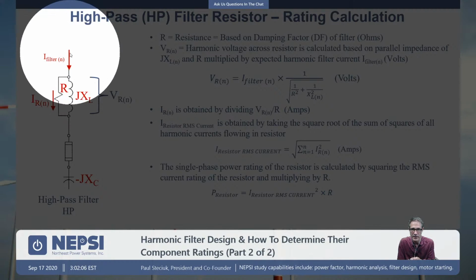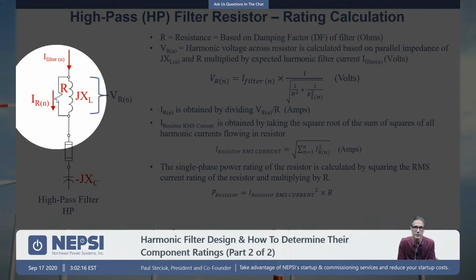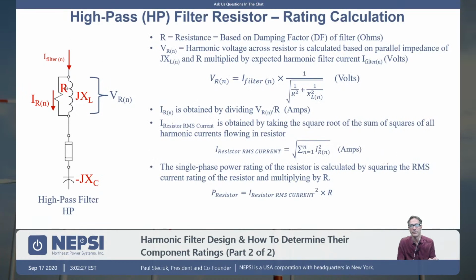Well, if I know what my harmonic filter current I filter in here, this is what the harmonic analysis program had predicted the harmonic current flow will be into the filter. We can use a couple current divider rules here to calculate how much current flows through the reactor, how much current flows through the resistor. And from there, we're going to be able to calculate I squared R, what the actual losses are in this resistor.